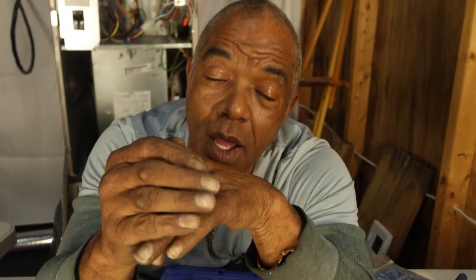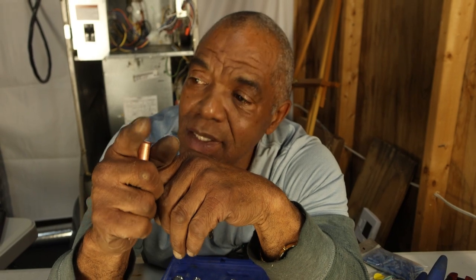Because as a service tech, you may have to replace an outdoor compressor because that's what failed on the system. You have to sweat that compressor out, which is to use a torch with flame and get that copper disconnected, and then you have to put the copper back into the new compressor, and you got to torch and flare it. And sweat it back in. When I say sweat, I mean using a torch to melt our brazing rod on the connection to seal it. It's called sweating. We're going to go over that now. That's going to take some practice. I'm going to show you how to do it.